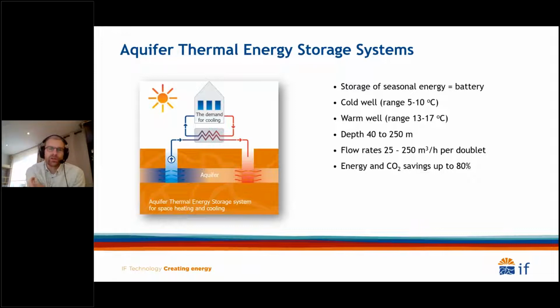Typical ranges of the cold well in the Netherlands are 5 to 10 degrees, and of the warm well 13 to 17 degrees. You can imagine that 17 degrees is not enough for direct heating, so you need a heat pump to increase the temperature levels. But 5 to 10 degrees is a perfect temperature for free cooling, for direct cooling of the building.